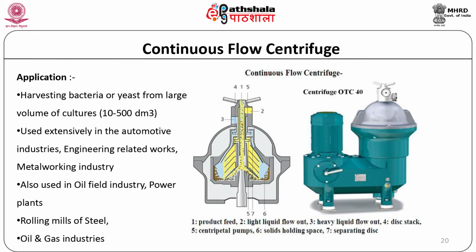Continuous flow centrifuge. This is relatively simple, high speed centrifuge. The rotor flows continuously. It is long, tubular, non-interchangeable. The rotor rotates continuously, medium enters through the rotating rotor and then the particles are sedimented against its walls. An excess clarified medium overflows through an outlet port. Application. It is used in harvesting bacteria or yeast from large volumes of cultures.